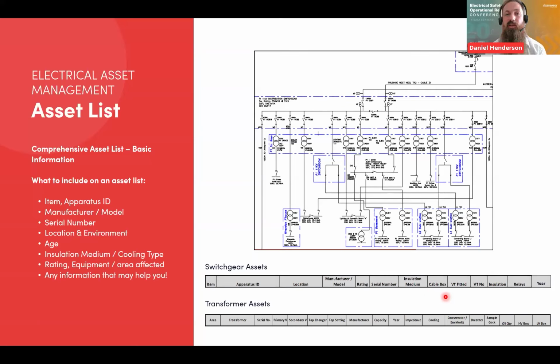I like to include the cable box. Typically newer installations are going to be air boxes, just a bolted on cover. Some older installations were pitch or compound bitumen filled boxes. Again, this will have an impact on your maintenance, on what you can and can't do. But it's also good information down the line. If you do have to do an asset replacement, one of the considerations will be how do you remove the pitch compound? It's quite a messy process, and heat is required. Or if you're replacing the whole box, is there an obsolescence issue with getting a replacement box? So it's good information to have.